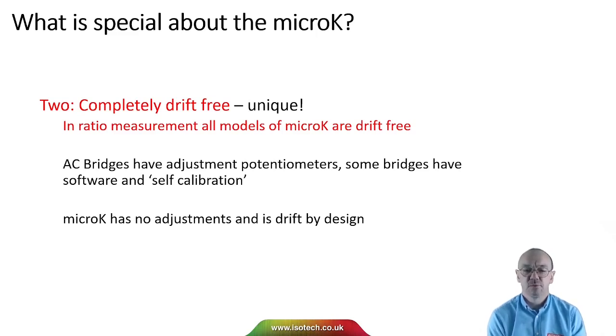So in ratio measurements, all the models of the MicroK are drift-free. That's because we've got a substitution topology, and we've got papers on that which we can share with you. So AC bridges, inside an AC bridge there are little potentiometers which you can adjust the filters and things. They move over time and need recalibration. Other modern bridges might have self-calibration, but the MicroK is by design drift-free, where there's no calibration in terms of the ratio accuracy of the MicroK. It's just something that comes from the design of the instruments, and there were no adjustments in software or hardware.